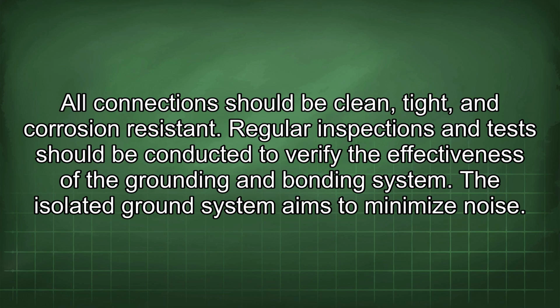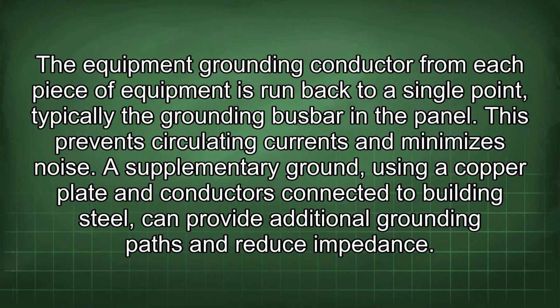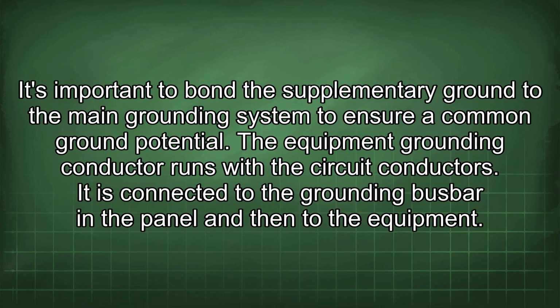The isolated ground system aims to minimize noise. The equipment grounding conductor from each piece of equipment is run back to a single point, typically the grounding busbar in the panel. This prevents circulating currents and minimizes noise. A supplementary ground, using a copper plate and conductors connected to building steel, can provide additional grounding paths and reduce impedance. It's important to bond the supplementary ground to the main grounding system to ensure a common ground potential.